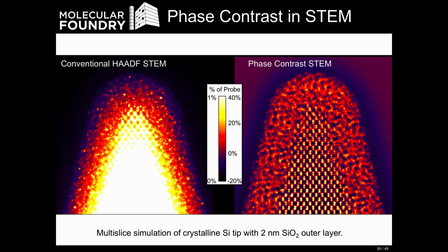So we're using 50% of our probe instead of less than 5%. If I blow up the contrast in the image on the left, now only plotting from 0 to 1%, you can see you do form pretty reasonable contrast in your amorphous region of the sample, but it's very, very dose inefficient - you'd need roughly 50 times more electrons to get the same signal to noise.